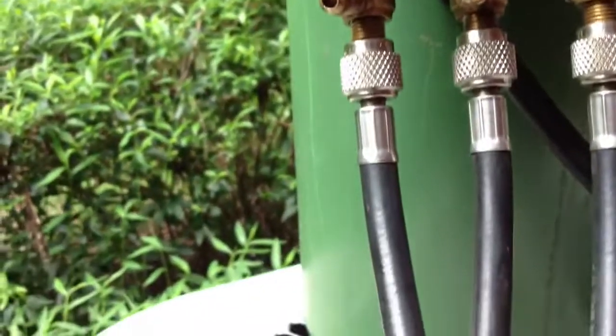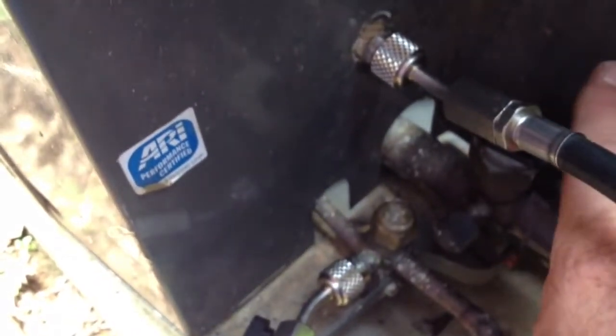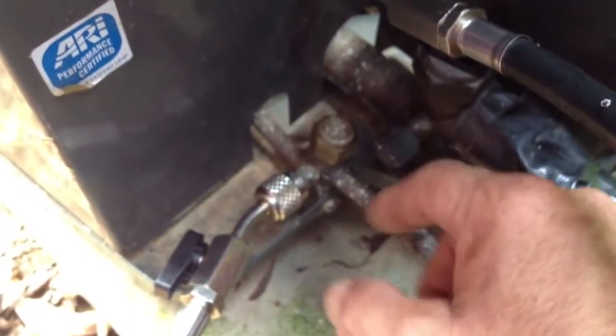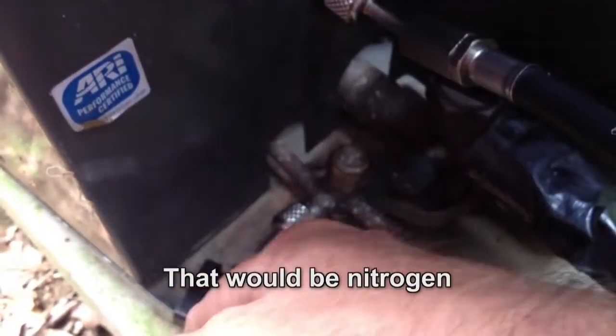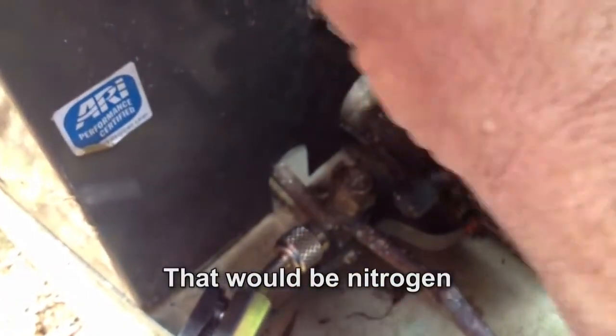Sorry, this thing is kind of shaky because I left my camera at home — using my iPhone. What I did was I took and I closed the liquid side and I closed the suction side valve off. And I pumped an equal amount of nitrogen into both sides. So I've got my low side on my unit and I've got my high side on the line set side.